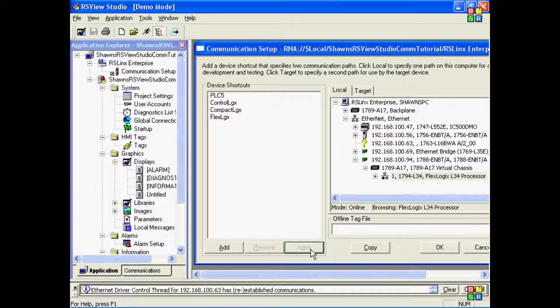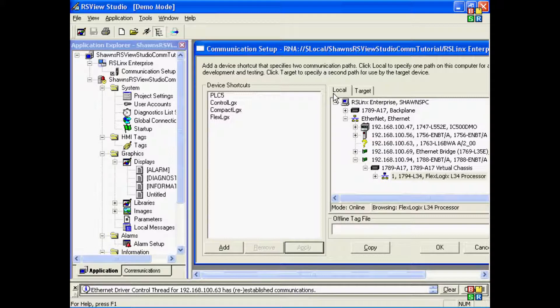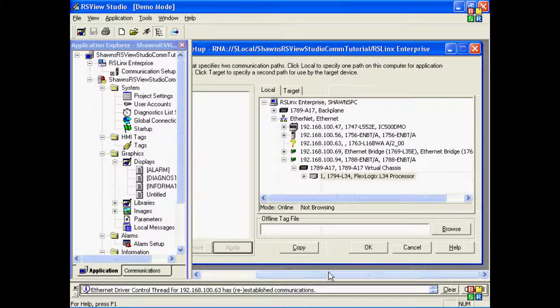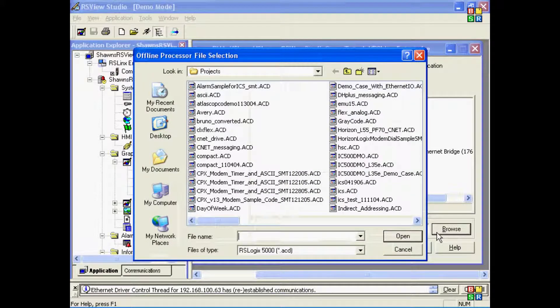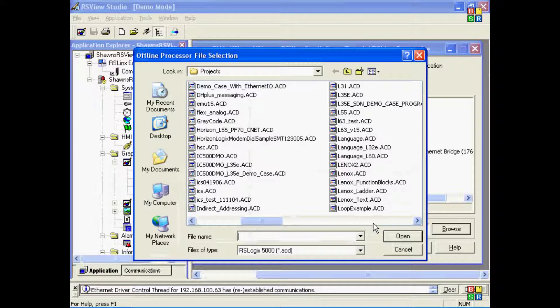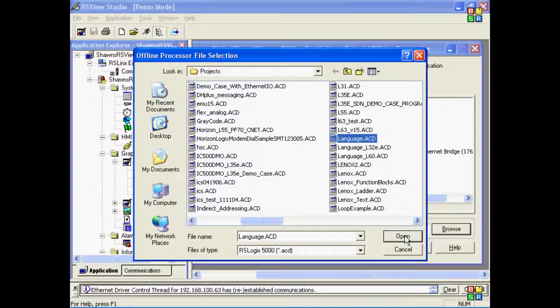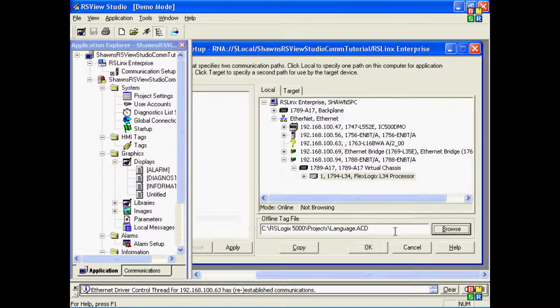Now one other thing I can do with Logix-based processors here on the local tab for development that I can't do with the older SLC 500 and PLC-5s is choose an offline tag file to browse for tags. This file must be located on your local hard drive. It cannot be located across the network.